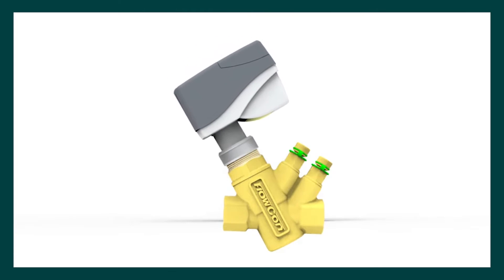Rotate the locking ring clockwise by hand until hand tight. The actuator is suitable for mounting upside down, but we recommend mounting the actuator above the horizontal, body facing upwards.